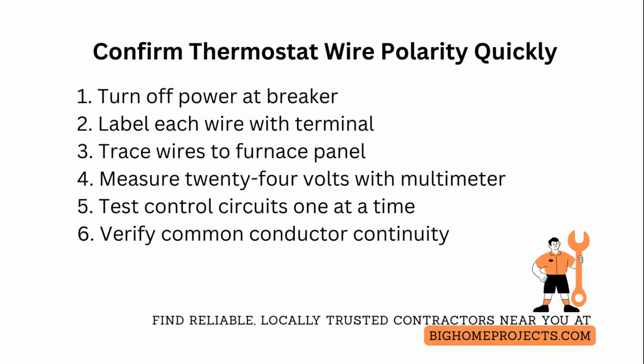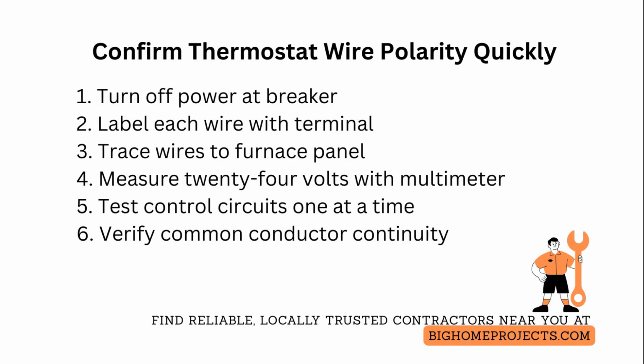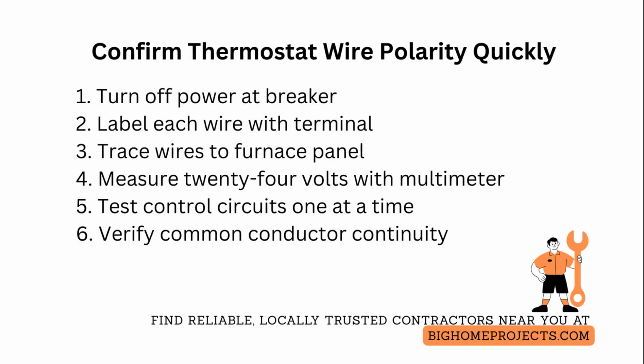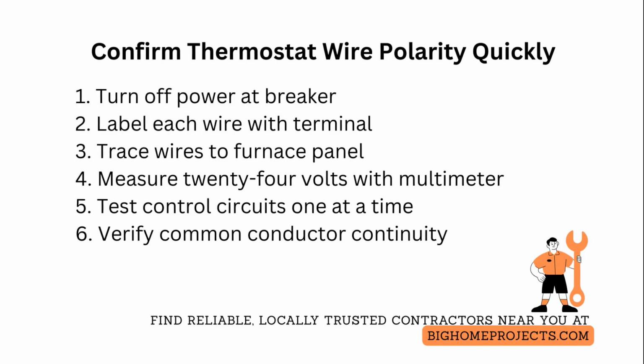Use a handheld multimeter set to low voltage alternating current to measure voltage between the common conductor and the power conductor. A working 24 volts indicates you have a proper transformer feed. If you see 0 volts, check transformer secondary terminals for continuity and replace the transformer if it is open.